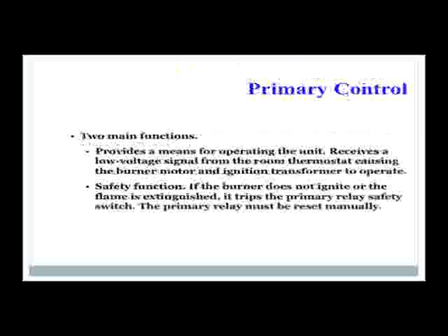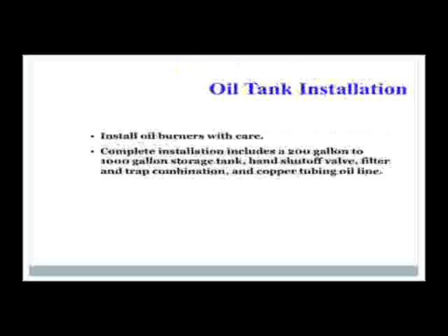The primary control has 2 main functions. It provides a means for operating the unit. It receives a low voltage signal from the room thermostat, causing the burner motor and the ignition transformer to operate. It also has a safety function. If the burner does not ignite or if the flame is extinguished, it trips the primary relay safety switch. The primary relay must be reset manually.